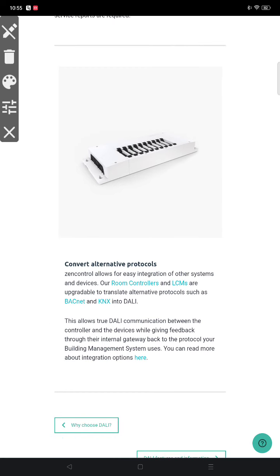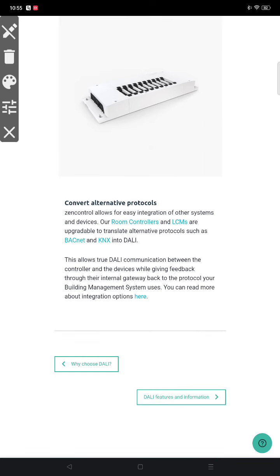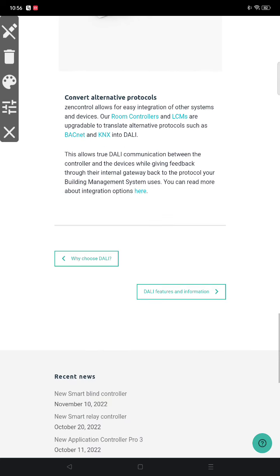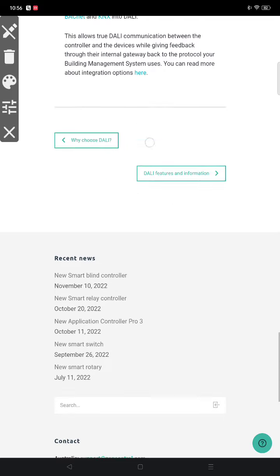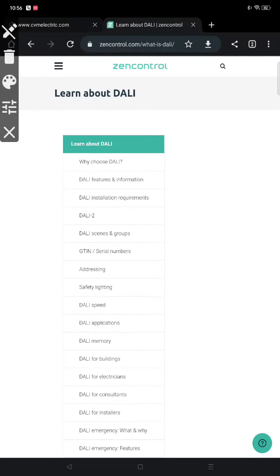Convert alternative protocols. zencontrol for easy integration. Okay, BACnet and KNX into DALI, and that can allow you to easily integrate all the other systems and devices. Our room controls, LCM, light control management, are upgradable and translate alternative protocols such as BACnet and KNX into DALI. This allows DALI communication between the controller and the devices while giving feedback. That's good now. Okay, and DALI 1, now DALI 2 is there.